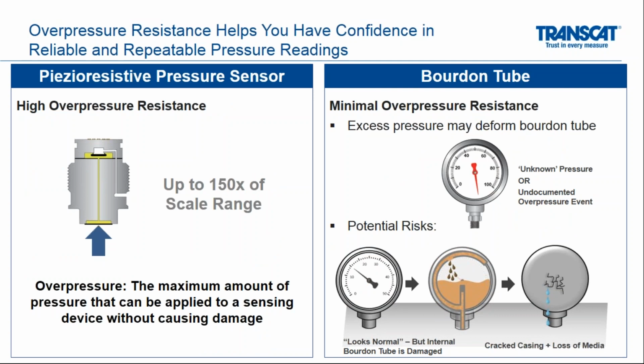Another one, talking about pressure, overpressure resistance. I should explain to this group, for those of you unaware, overpressure is not saying that all of a sudden pressure escapes or leaks out. What it's saying is that this is the amount of pressure that the gauge can handle without being damaged. So let's say that you have a 15 PSI gauge. If your overpressure was 30 PSI, that means if you went to 31 PSI, your gauge is now irreversibly damaged.